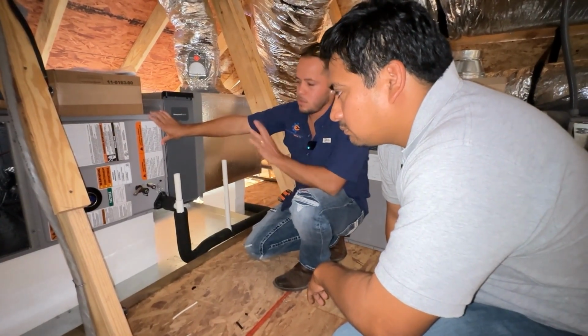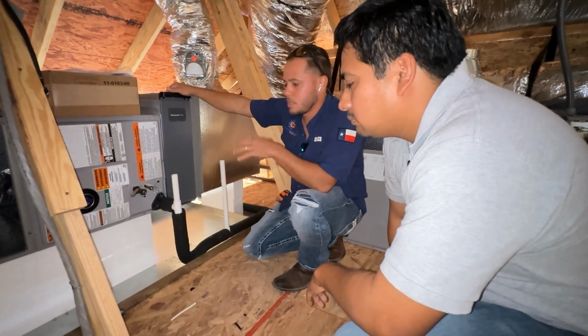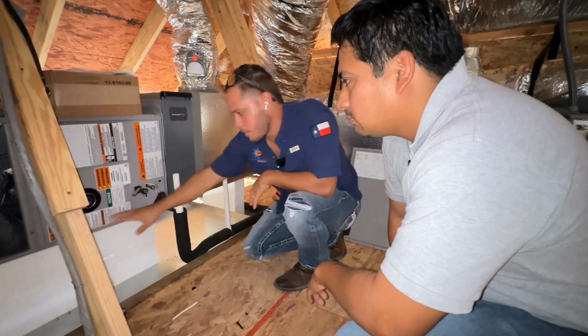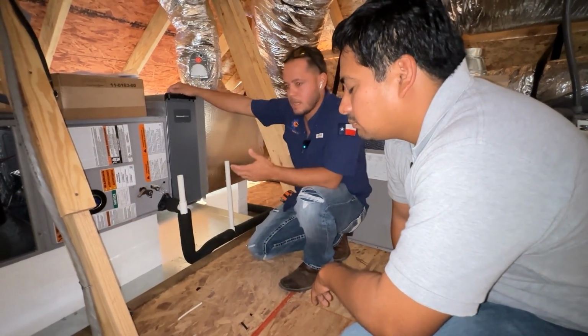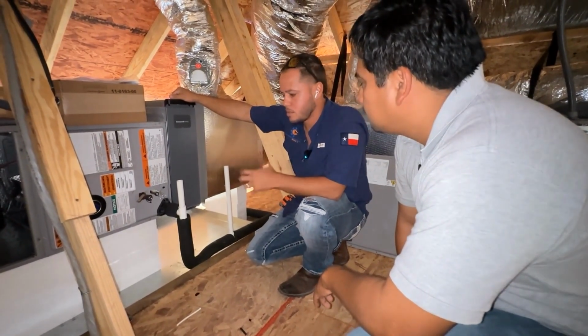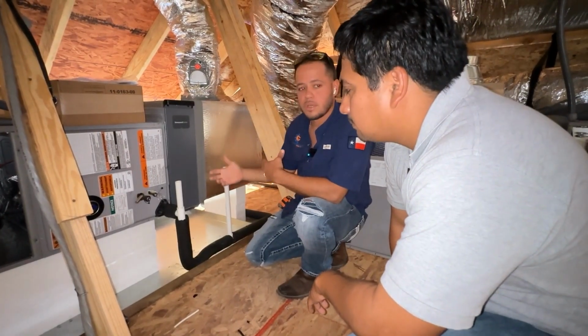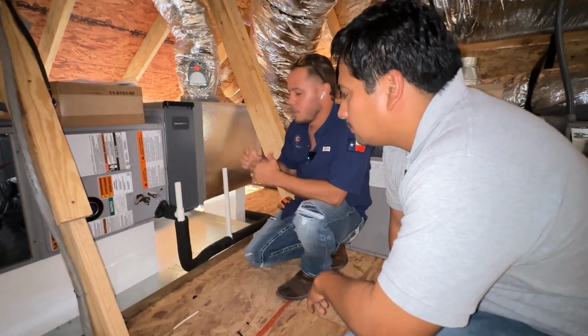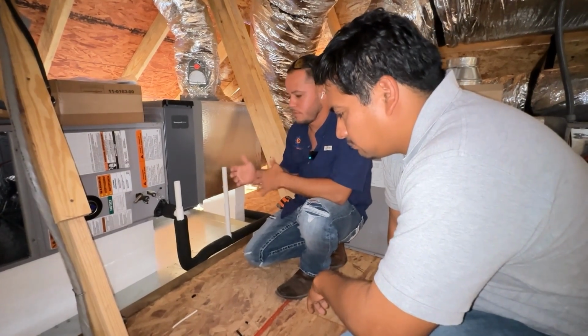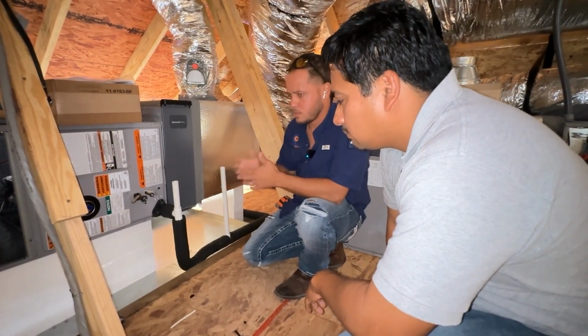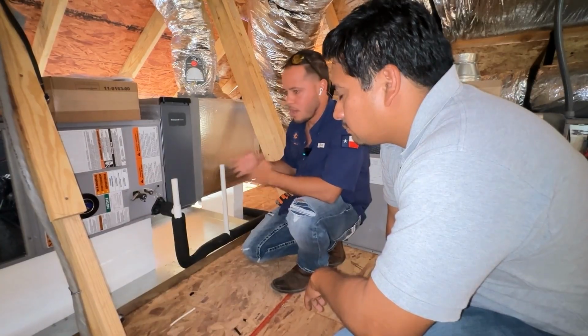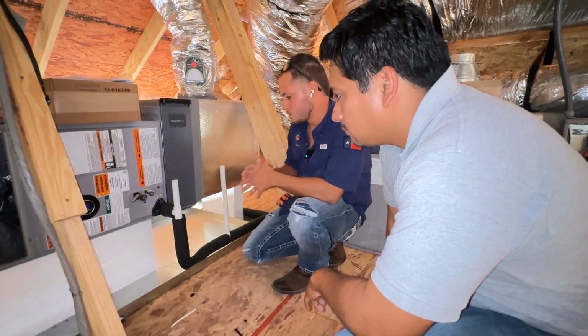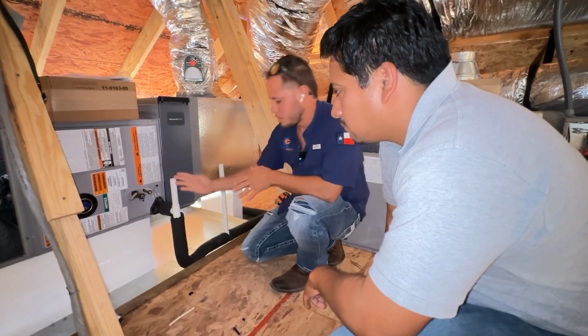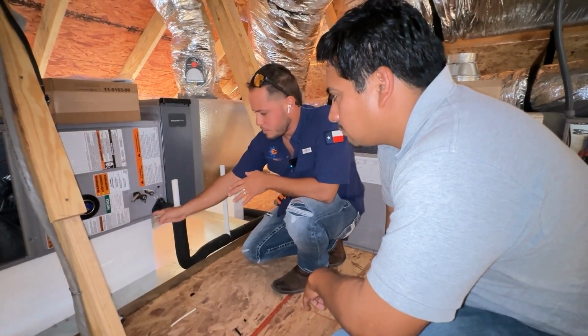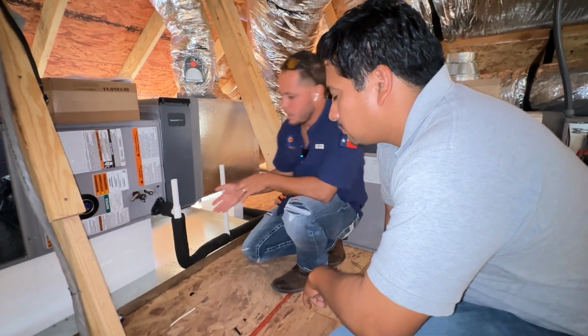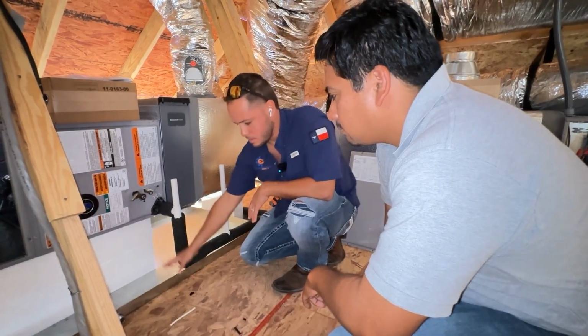These systems, and all HVAC systems, condense water into a primary drain pan inside the unit. With time, dust starts to create some slush inside the pipe, and that's where you start having clog issues with the drain line. Here in Austin, there are many different ways you could do this, and I could get into that in a little bit. But the way we like to do it is this is the primary drain line, we like to put a secondary float switch here in the secondary drain line, and then another float switch in the secondary drain pan.